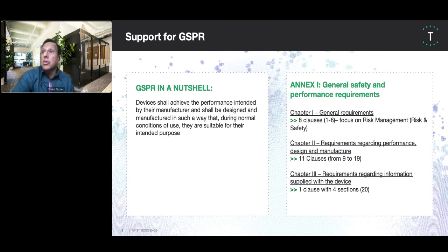So GSPR in a nutshell, so devices shall achieve the performance intended by their manufacturers and shall be designed and manufactured in such a way that during normal conditions of use, they are suitable for their intended purpose. Very key thing. All auditors are going to look at that statement and ask you to justify that your product is suitable for the intended purpose. And as Andres had mentioned, there's about 20 main clauses in the GSPR.